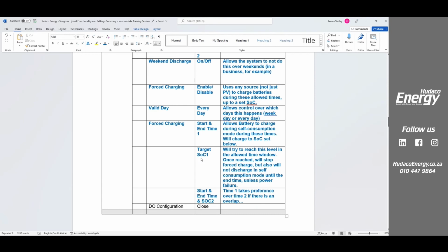An example of this might be, every day from 7 o'clock to 8 o'clock, I want you to check to see if my batteries are at 80%. If they're not at 80%, top them up to 80%. Okay, and keep them at a minimum of 80% until the end of that time, until whatever time I said, 8 p.m. Okay, where this might be used is maybe it's rainy for whatever reason, and we're expecting rain for 2 weeks, and we're worried that the solar power won't have my batteries at the right level, but we do know that we've got load shedding coming later. So every day, I just want you to top up my batteries. Okay, we call that forced charging, and we can do that twice a day.